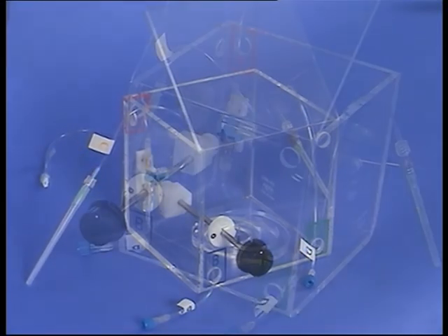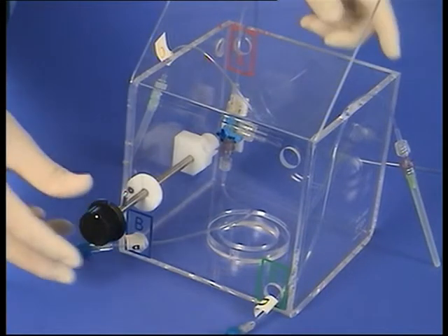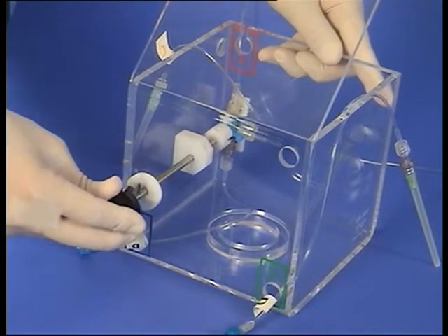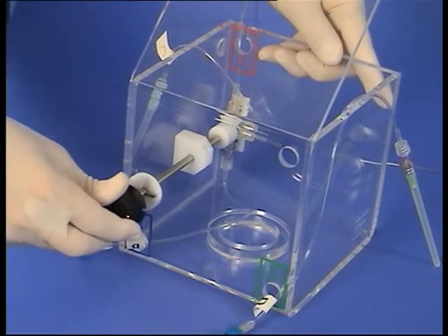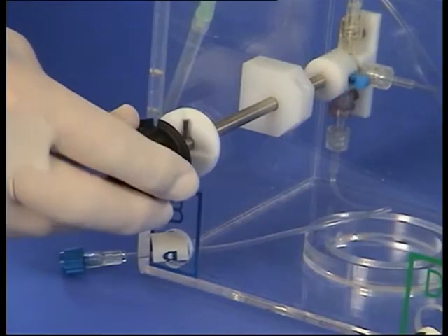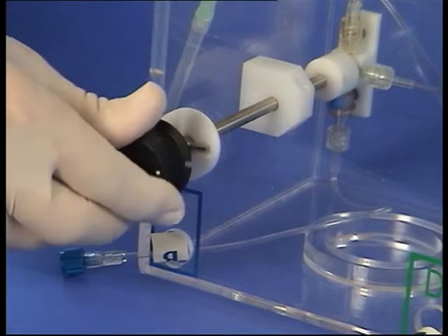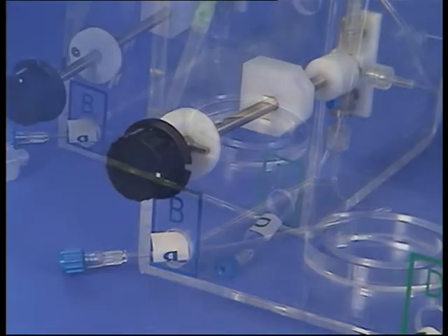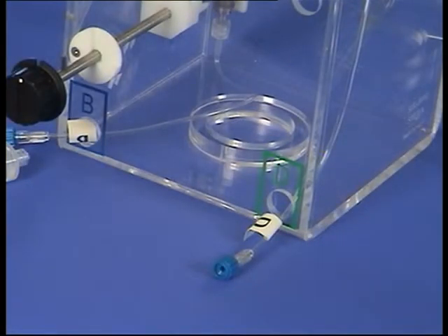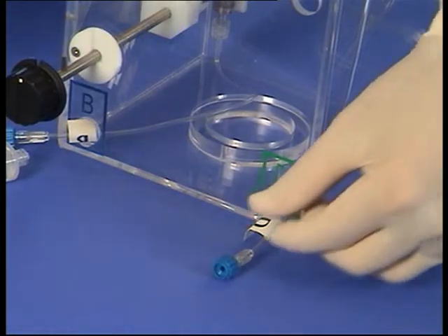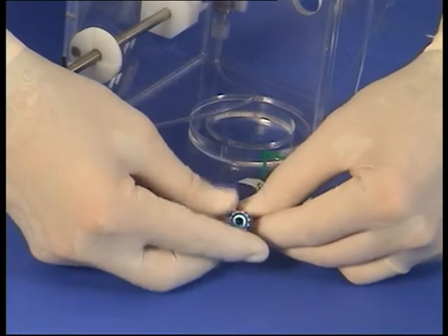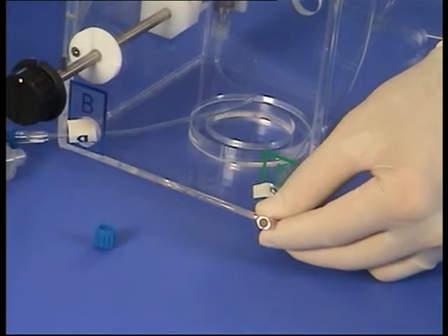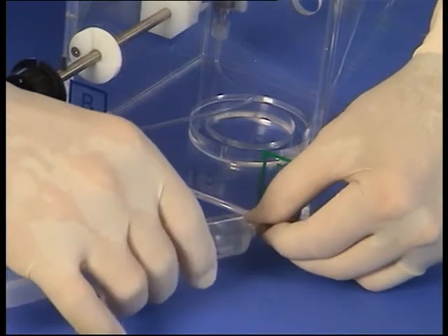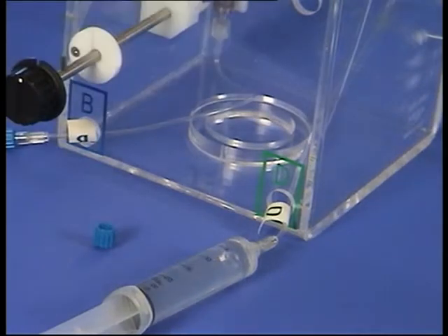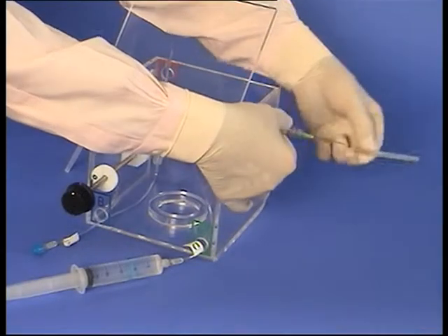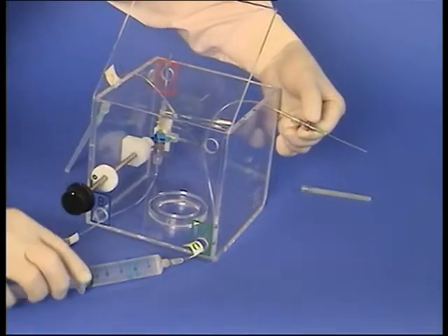With the lines in their respective places, engage the control knob. This is done by firmly seating it against the handle of the stopcock. The control knob and handle should now only be able to turn 90 degrees. Before delivery can occur, all lines must be primed with water for injection. In priming all the tubing, it is essential to remove all air bubbles. Attach a 20 milliliter syringe to line D on the outside of the box. Loosen or remove the needle cap and slowly push through some water.